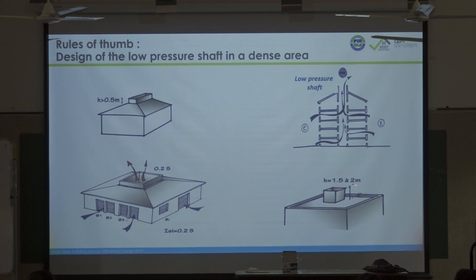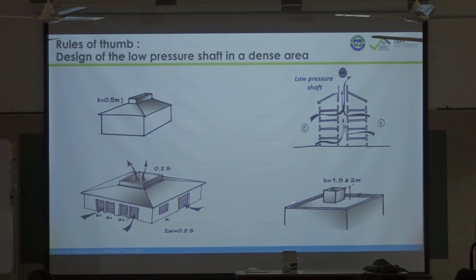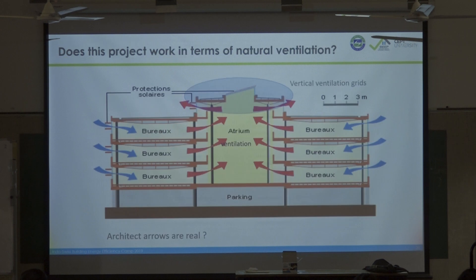There is a shear layer located at the first meter off the slope of the roof. To get a stable wind effect, you have to design the shaft above this shear layer — meaning with a height of 2 meters you can catch the good wind signal. The theory will be available and I will be here till the end of the week to help you design a low pressure shaft.